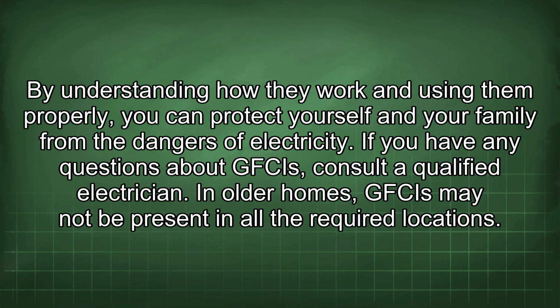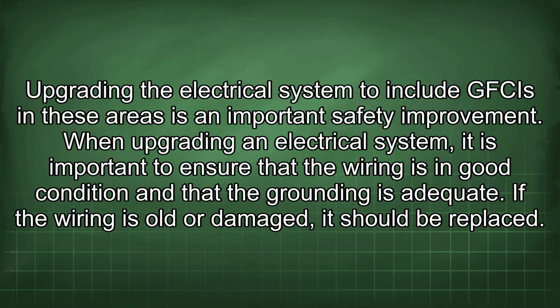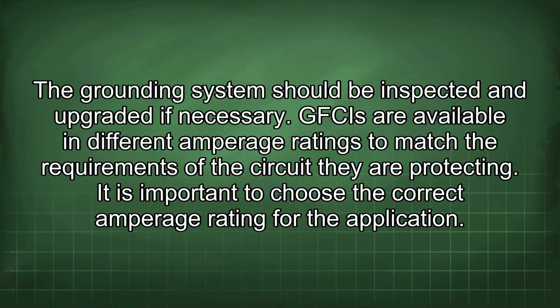In older homes, GFCIs may not be present in all the required locations. Upgrading the electrical system to include GFCIs in these areas is an important safety improvement. When upgrading an electrical system, it is important to ensure that the wiring is in good condition and that the grounding is adequate. If the wiring is old or damaged, it should be replaced. The grounding system should be inspected and upgraded if necessary.